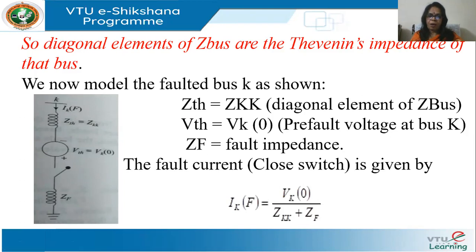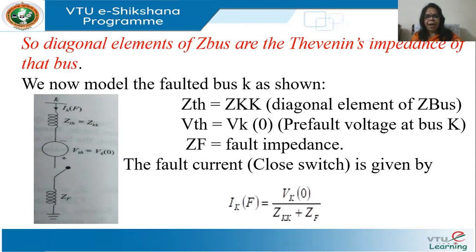I have calculated the short circuit current. You can do it at any bus, because K is just the bus number. Once you have the load flow voltages at all buses and Z_KK as the diagonal element, you can calculate the fault current for a short circuit at any bus. The second job is to calculate the change in bus voltages because of this fault.